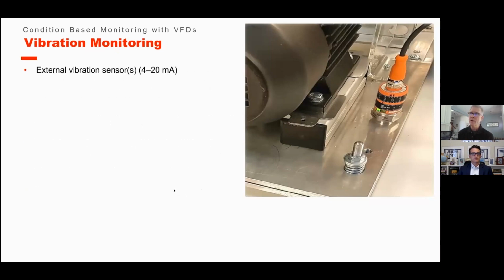One thing you'll notice right off from the picture is that on the right-hand side of the motor feet, there's a vibration sensor mounted. Now, this is the only monitoring value that we need an external sensor for. And any sensor will work, as long as you have an analog sensor coming back, either 4 to 20 milliamp or 0 to 10 volt. Most common is 4 to 20 milliamp, a current source coming back. And they're usually velocity or acceleration type sensors.